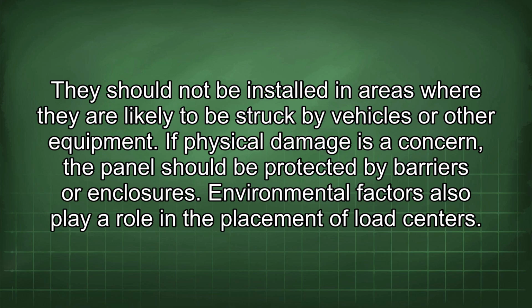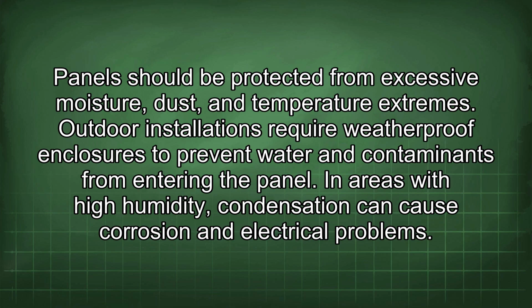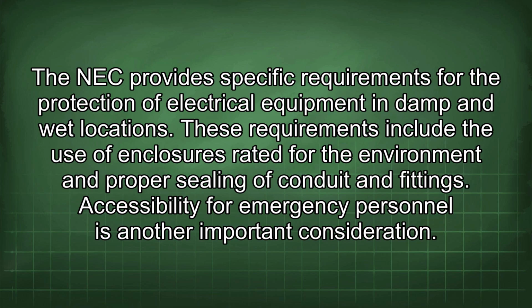Environmental factors also play a role in the placement of load centers. Panels should be protected from excessive moisture, dust, and temperature extremes. Outdoor installations require weatherproof enclosures to prevent water and contaminants from entering the panel. In areas with high humidity, condensation can cause corrosion and electrical problems. The NEC provides specific requirements for the protection of electrical equipment in damp and wet locations. These requirements include the use of enclosures rated for the environment and proper sealing of conduit and fittings.